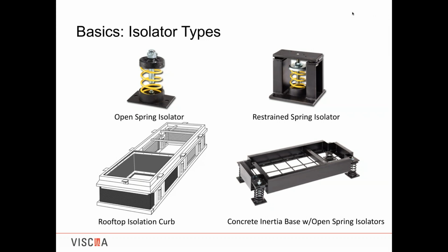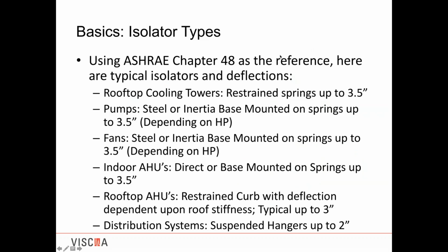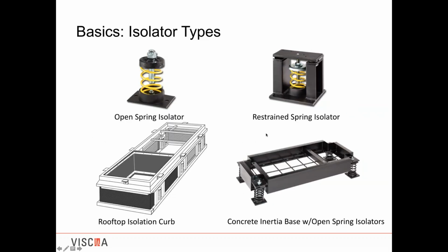Now in the lower right, that's a concrete inertia base with open springs. I had mentioned earlier with pumps, Chapter 48, you see here, pumps are on steel or inertia bases, and same with fans. When we talk about inertia bases, we're talking about a component that has the ability to add mass into it, and we add that mass with concrete. The concrete is installed in the field, so what would ship out to the installer is a concrete form with rebar in it. They fill it with concrete in the field. After it cures, they can attach the pump or the fan to it before they lift it.